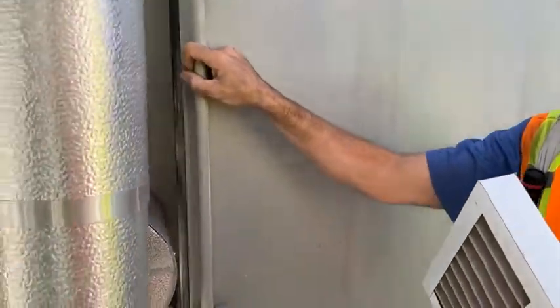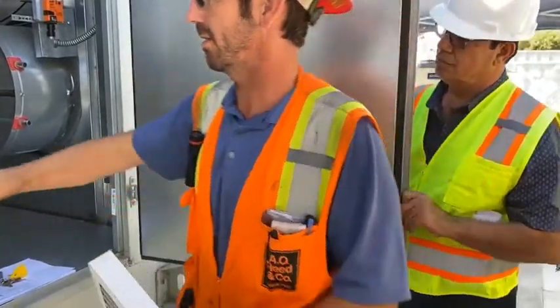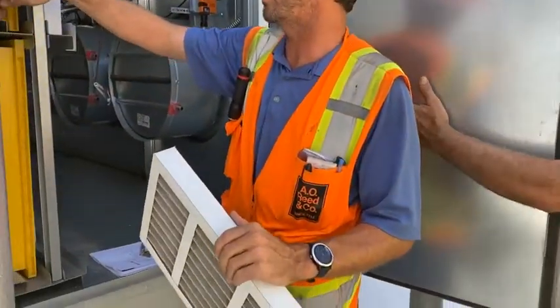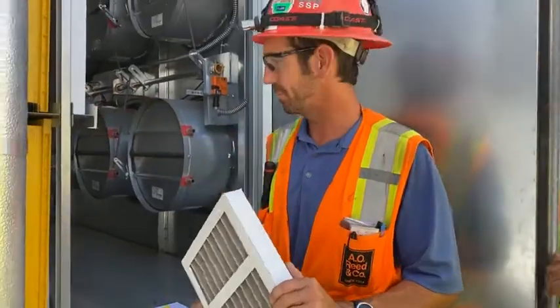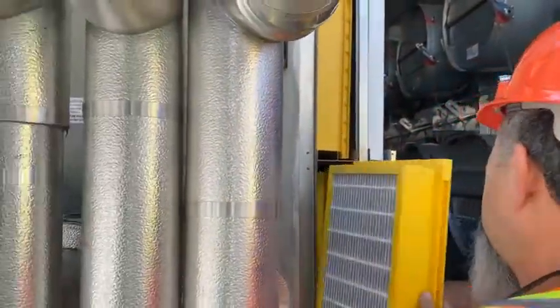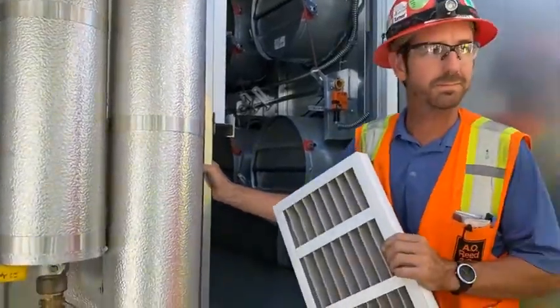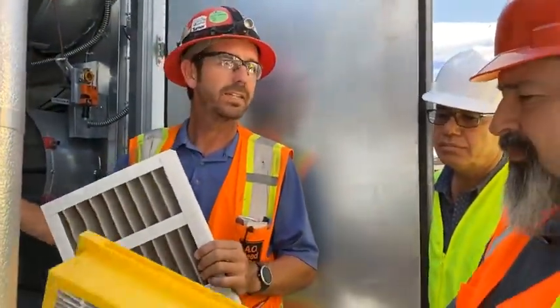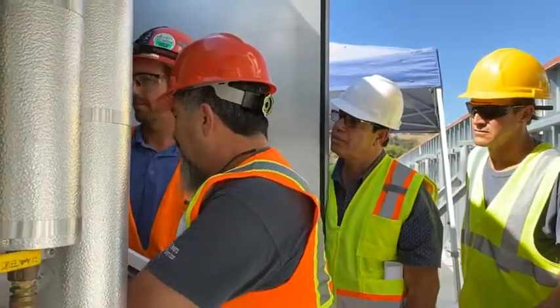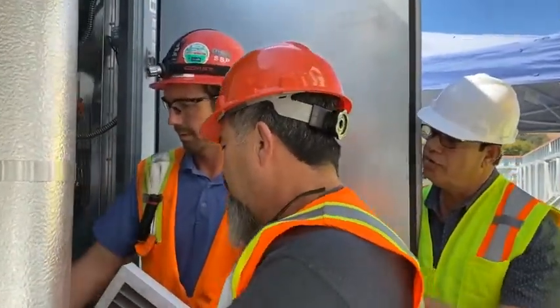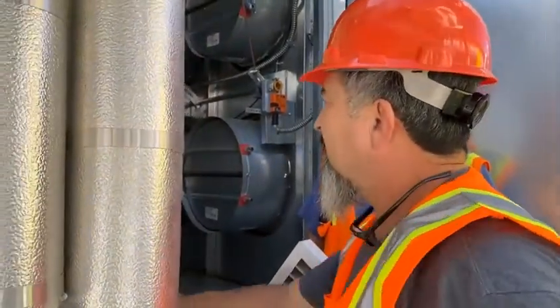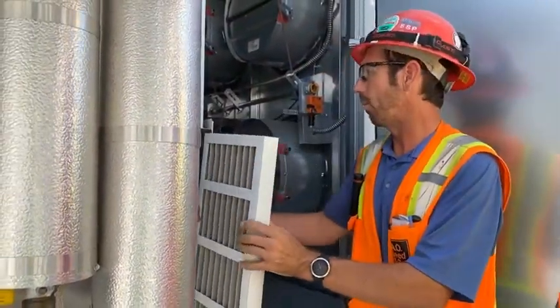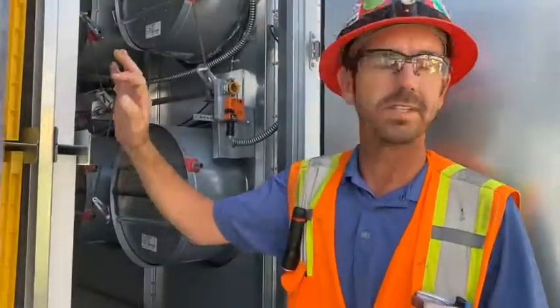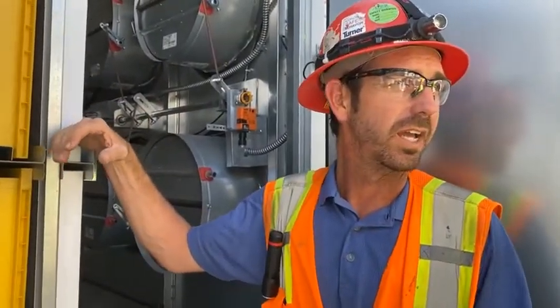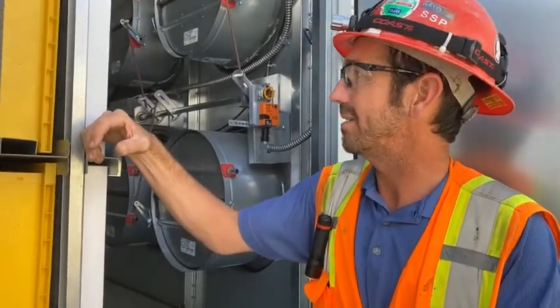MERV 8 is 2-inch, MERV 13 is the 4-inch filter. You can install box filters on the MERV 13s or cartridge. Right now these are set up for cartridge. If you needed a box filter instead of the cartridge, you can just remove this trap. Let me see this. Can I open it? Sure. So that's a MERV 13. It's a thicker, lower micron filter. Right. Okay. This is a cartridge style. So can you wash them or just replace? No, these are non-washable filters. They'll need to be replaced. They're expensive. And then what you can do is follow the health and services recommendations on filter changes, or as needed. Okay.